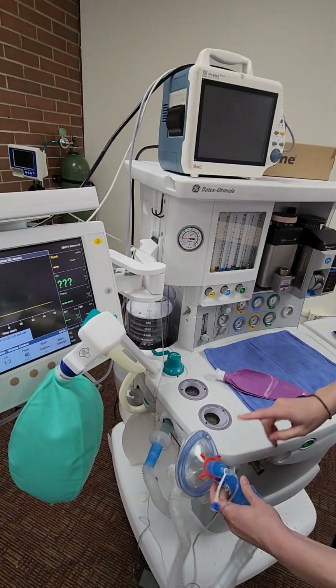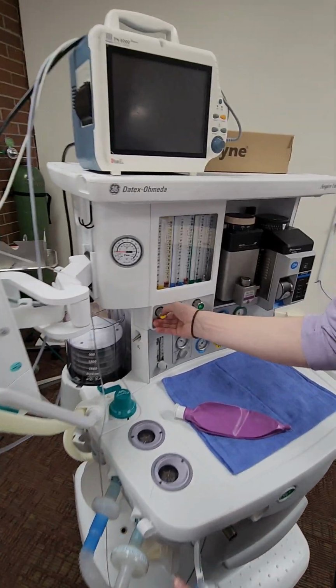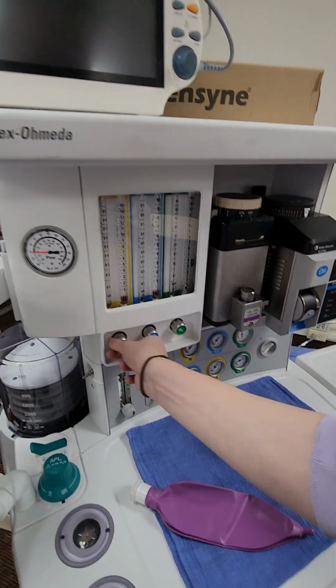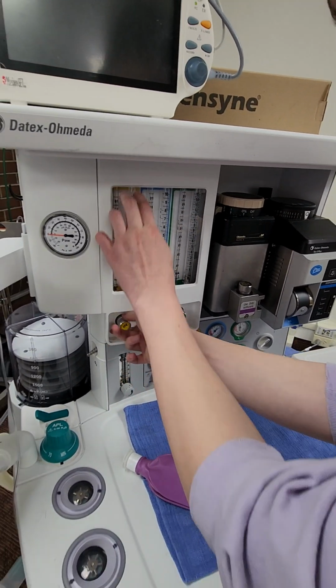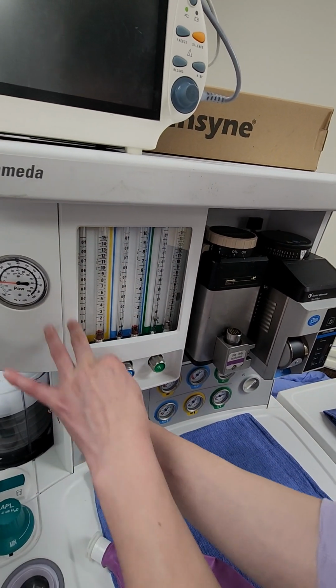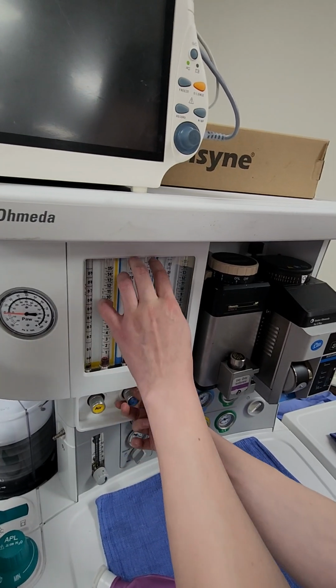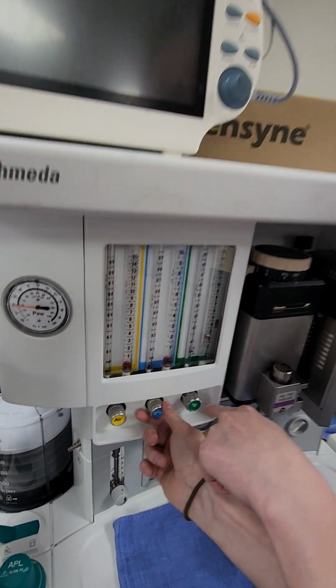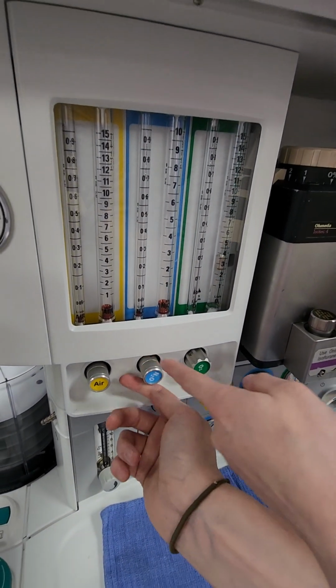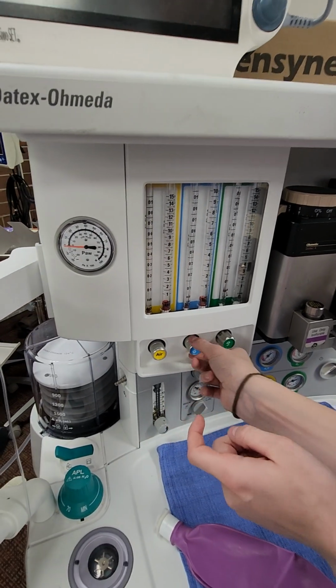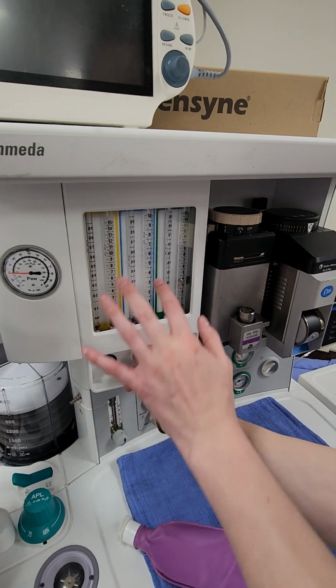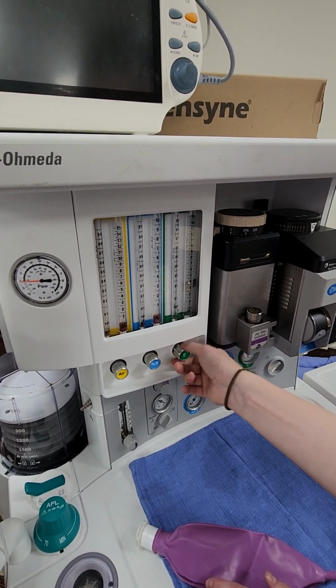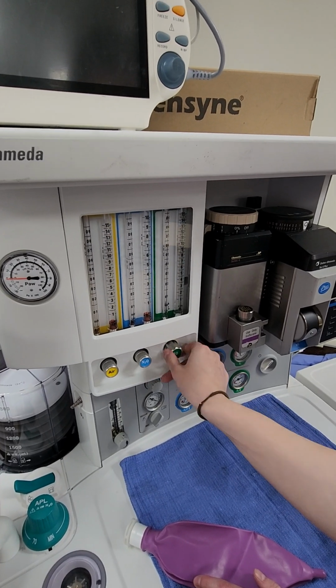Actually, before that, you want to check your Thorpe tubes. So you'll turn these on all the way. These should go all the way to the top, and then you should close them again. So this should go all the way to the top, and close it again. And this also you can see is checking your link 25, so you can see oxygen, nitrous. It prevents a hypoxic mixture. So then you close your nitrous again, turn it all the way closed, run oxygen all the way to the top.